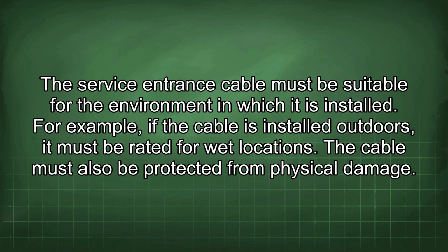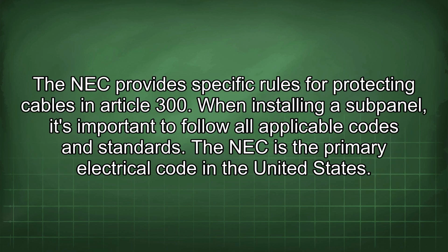The service entrance cable must be suitable for the environment in which it is installed. For example, if the cable is installed outdoors, it must be rated for wet locations. The cable must also be protected from physical damage. The NEC provides specific rules for protecting cables in Article 300.